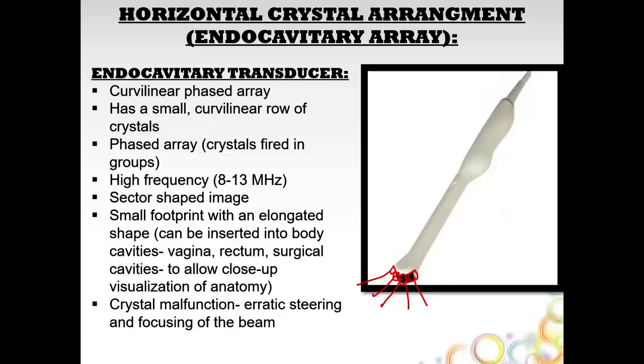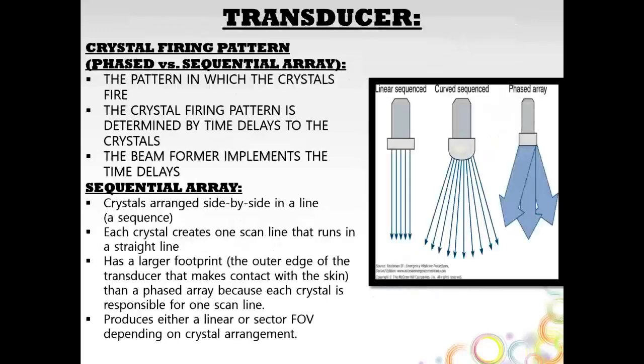These are high-frequency transducers, 8 to 13 megahertz, and we use these in body cavities. So you can use them in the operating room, you can use them in the vagina, you can use them in the rectum. And this lets us get a close-up visualization of anatomy. Now, when a crystal goes out with these, not only do you get a line of dropout, but you're also going to get some erratic steering and focusing of the beam. So you'll notice right away if a crystal goes out.